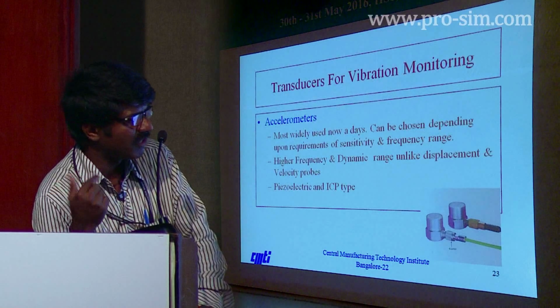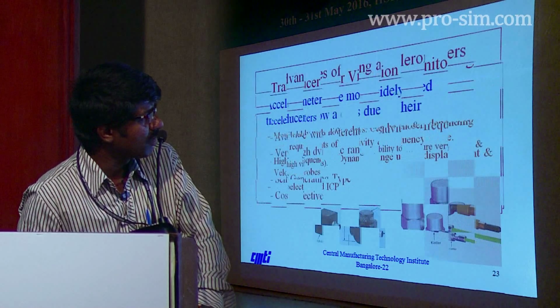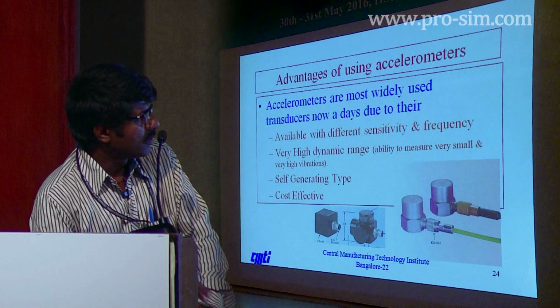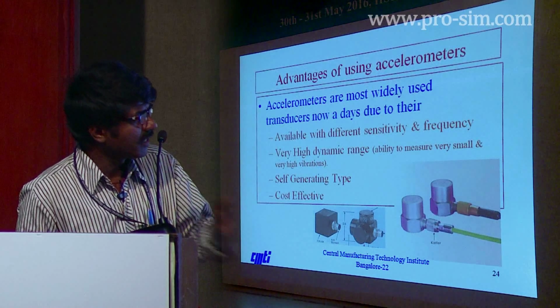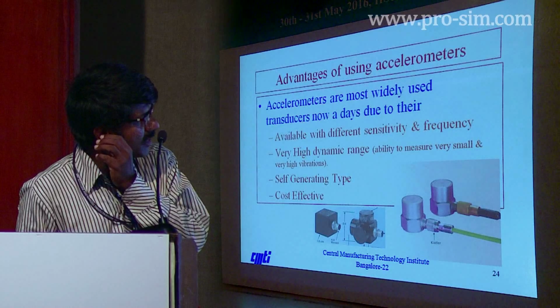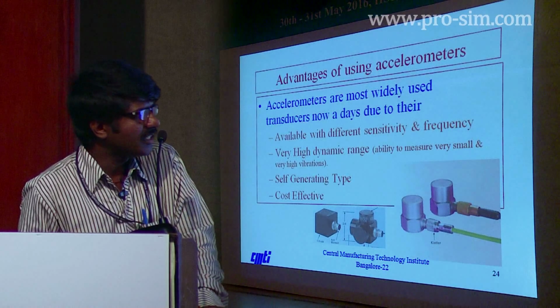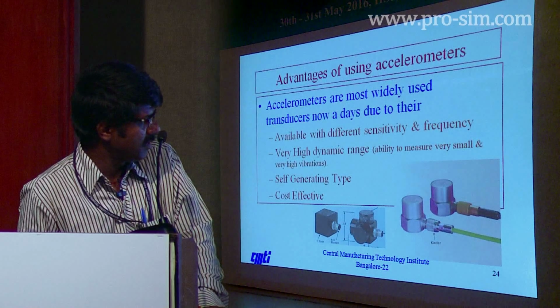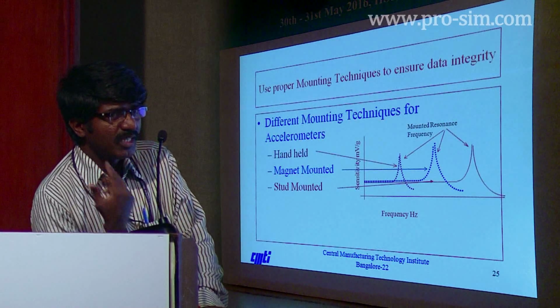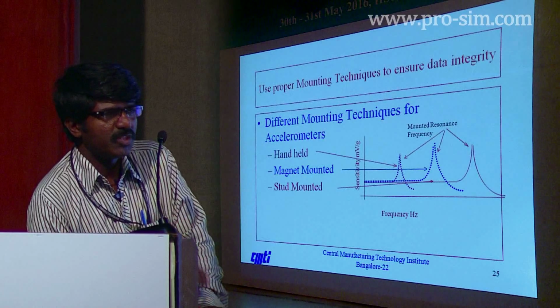Directly you can connect it to the analyzer and you start collecting the vibration data. It doesn't require any power supply. It is a self-generating type. If you are using ICP, you have to supply 4 milliamps of current to make it operative. Next comes how to mount the sensor on the machine tools.